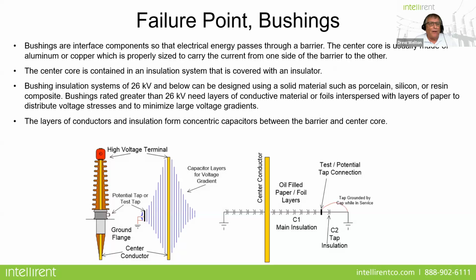Well, they're the interface components that allow electricity and energy to pass through a barrier to the inside of the transformer. And of course, this is true for bushings on anything, bushings on circuit breakers, bushings on reactors. But the core is usually made of aluminum or copper, and it's properly sized to carry the current from one side of the barrier to the other. The center core is contained in an insulation system that's covered with an insulator.